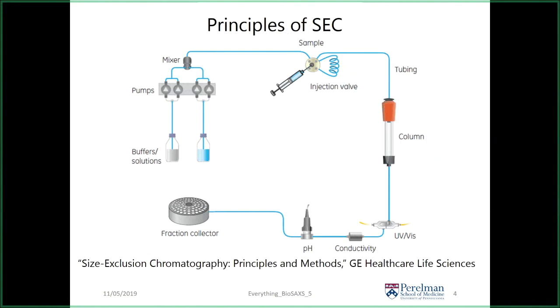The general setup: you start with a buffer reservoir. For light scattering and SAXS, make sure buffers are filtered — at least 0.2 micron or finer. You'll also want to degas them, because buffers will degas if temperature or pressure changes, and those gas bubbles will scatter. You have a pump system, an inline injection valve to introduce sample, and then the column — the mode of separation — which comes in many varieties.